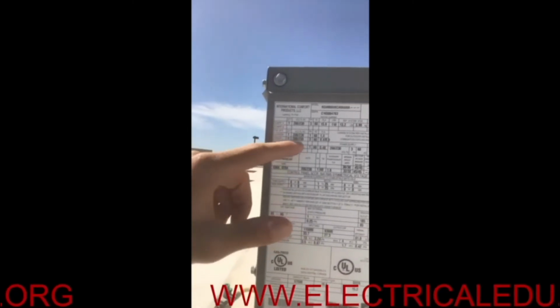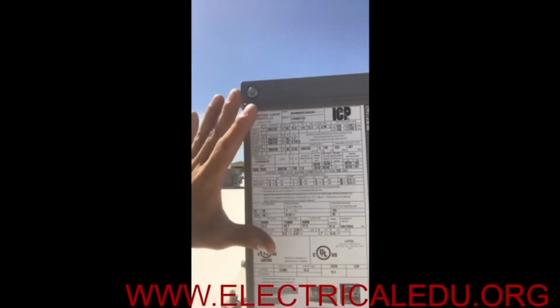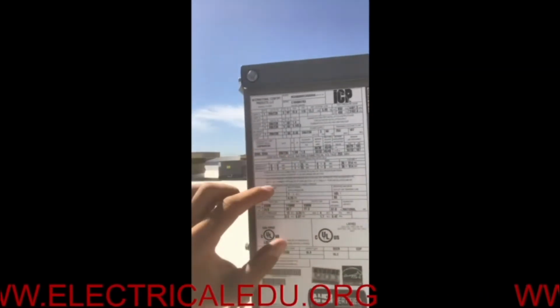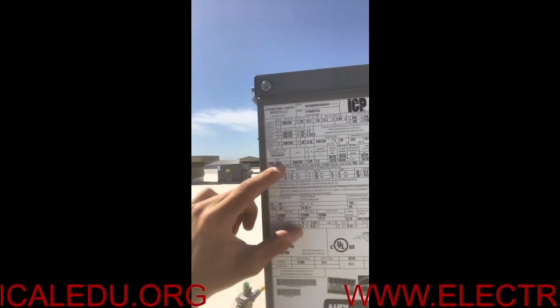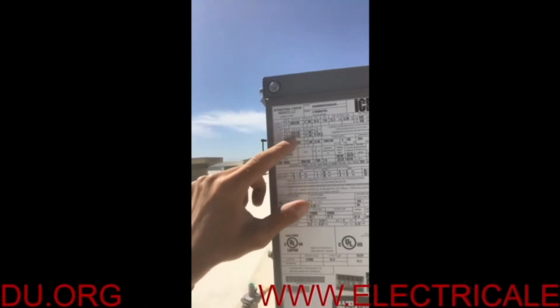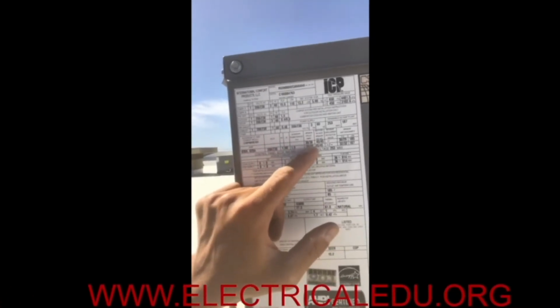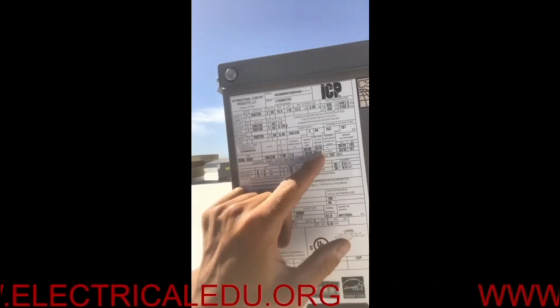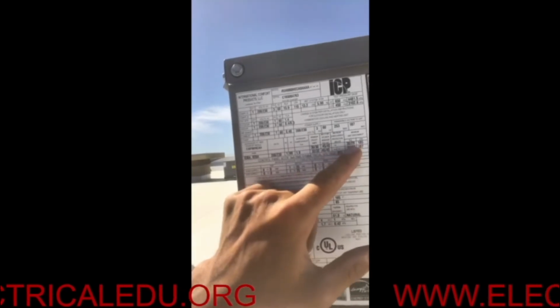So you see this, there's a lot of information here. You got 3-phase, you got 208, 230. You got all the information on here, somewhat more than what you think you might need. On this application, you have a few different things that show amperage, 30 and 28 amps. That's going to have to do with your voltages. And then over here, you have minimum circuit ampacity 30 to 32 amps, maximum fuse or HACR breaker 45 amps. And then you got your full load amps. So there's a lot of codes involved in that, and I'm going to explain that with my code book.